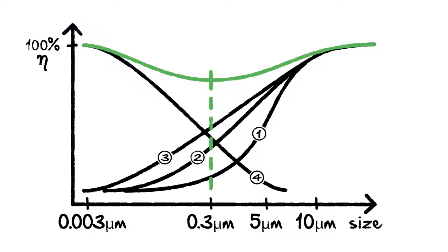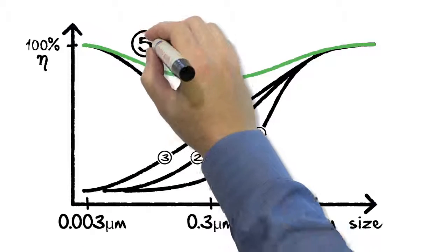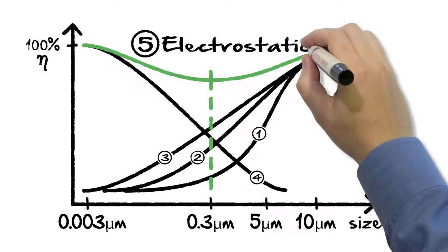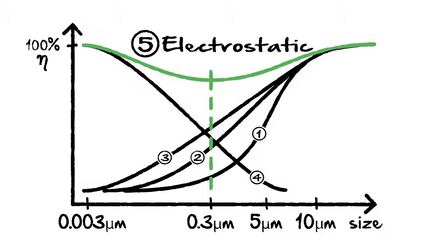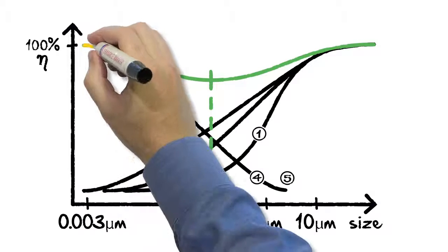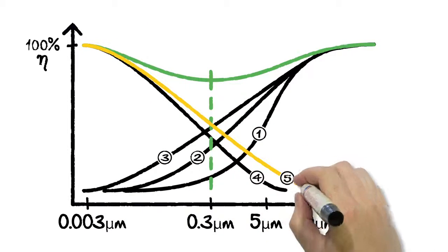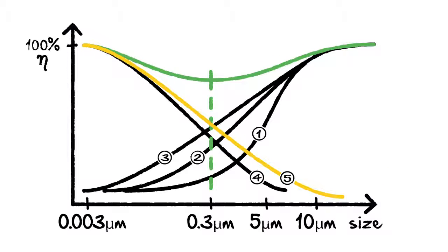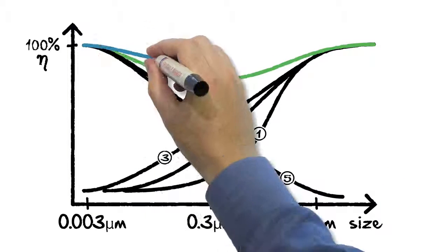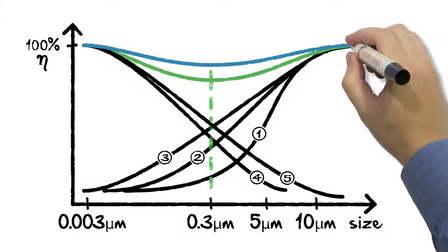What we're able to do by adding our electrostatic attraction force, the 5th force, is that it also works better for the smaller ultrafine particles, but it's not as effective when particles are really, really big. So we're adding something with high efficiency here and making a new total efficiency of the filter where we're adding this 5th capture force. We get a filter curve looking like that.